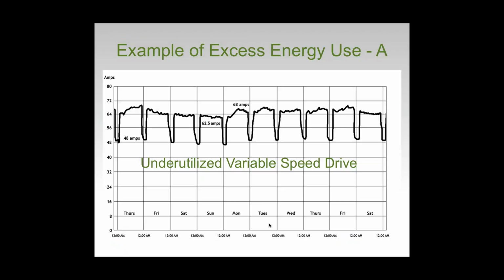As an example, this particular graph is plotting the energy usage of a supply air fan, measuring in this case the amperage that the fan is consuming. Follow me through here for a minute. Here we are in weekdays. We use an average of 68 amps during occupied hours. Notice here are my unoccupied hours at night. And then on the weekends, notice that we've slowed that fan down a little bit. We've taken it from 68 amps down to 62.5. We've reduced its controller operation by roughly 10% when we look at this.